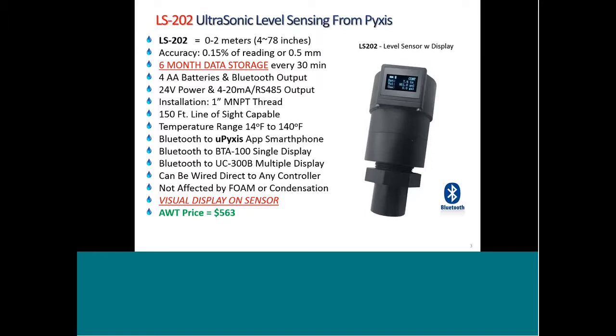But for those applications where wiring and distance to the controller is an issue, or the customer's not interested in providing conduit or wiring runs, this unit can be run in a battery operation mode with 4 AA batteries. And when in that mode, the device can be set to Bluetooth functionality. It has 2 different Bluetooth modes that we're going to talk about. One's called a periphery mode, and the next is called a beacon mode. And we'll talk about the differences between the 2 of those. But in essence, in the Bluetooth mode, you can utilize the Pyxis app on your smartphone or your PC, which is a free app available for download, and communicate directly with the tank level monitor.